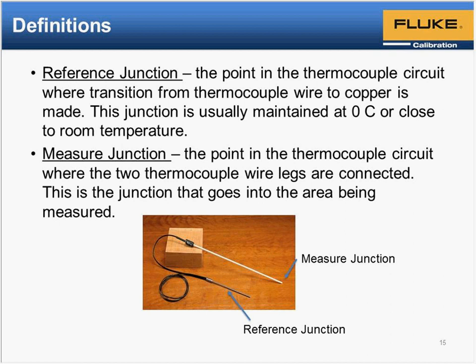As a matter of fact, the 1586A has a feature for this. It's basically the concept where all the couples are bundled together into a heat source, and then you push a button and it automatically detects the difference between them and normalizes all of them. So it does a quick calibration. I don't remember all the details, like if that applies over multiple temperatures or if that's just at one temperature. Absolutely, that application is applied in many different scenarios, just describing temperature gradients inside of an air duct.